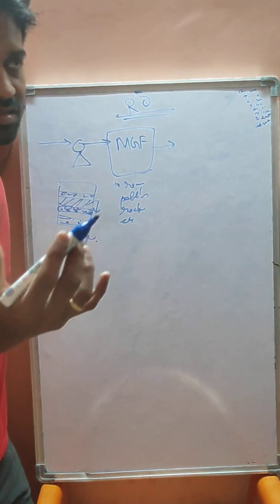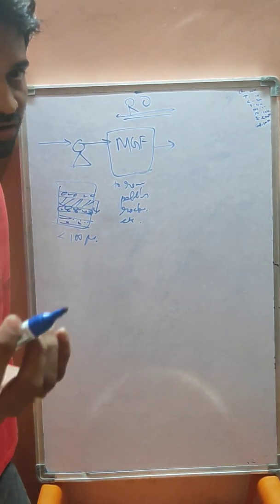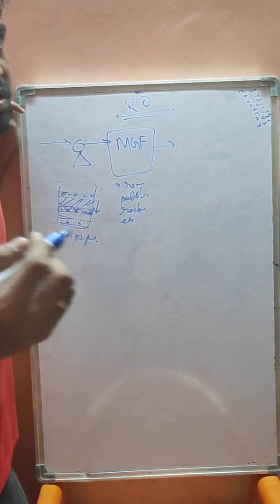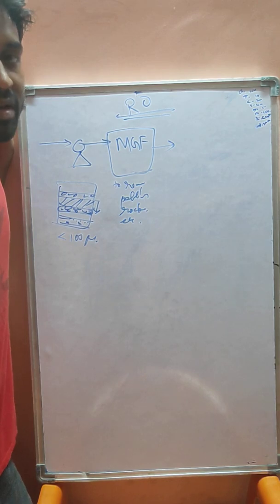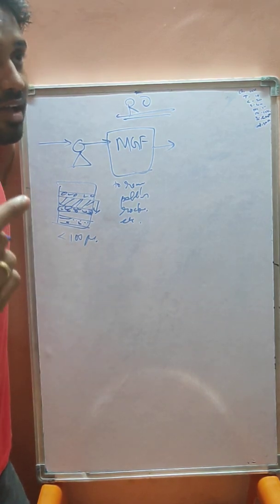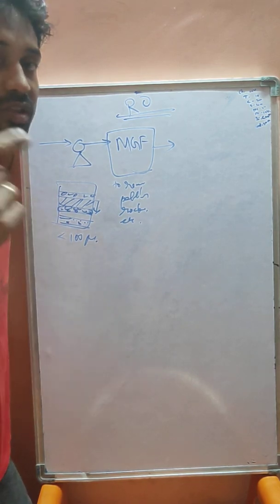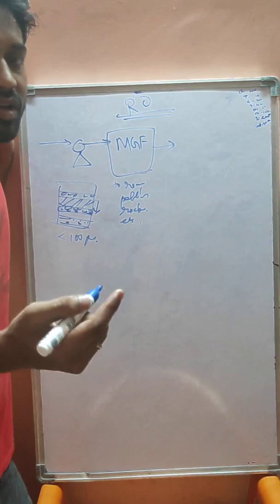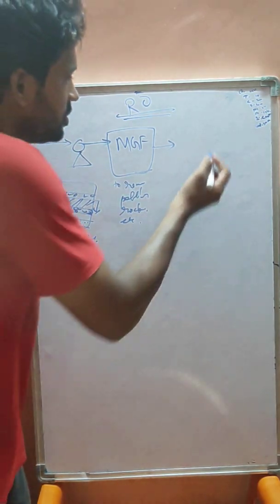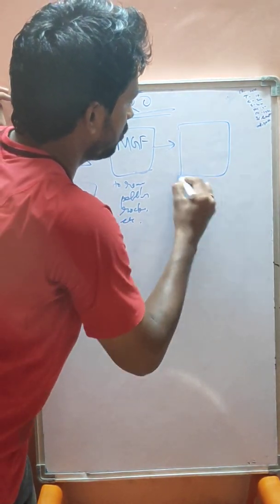Here we have two cases. You can use an ultra filter or an activated carbon filter. It depends on the plant. If you go for a refinery or petrochemical industry, mostly they will go for an ultra filter also. Either they may use both filters together, or any one of them based on the purpose. If it is a small scale industry, we can directly go for an activated carbon filter. So here they are going for the activated carbon filter.